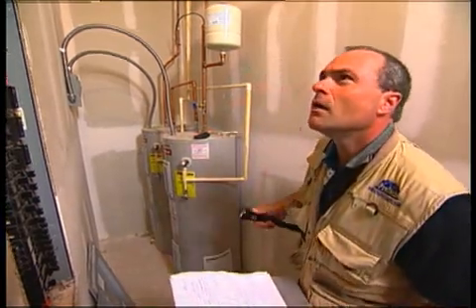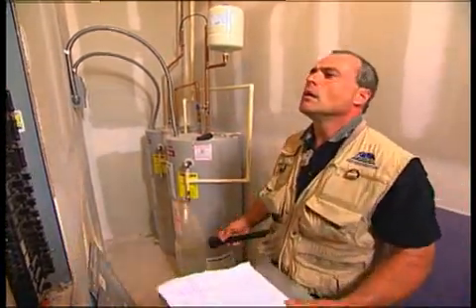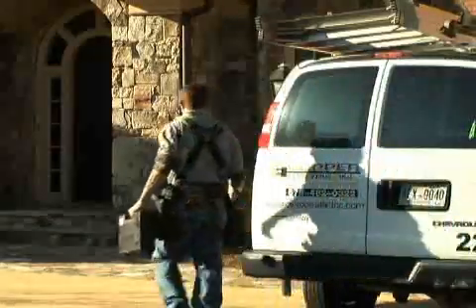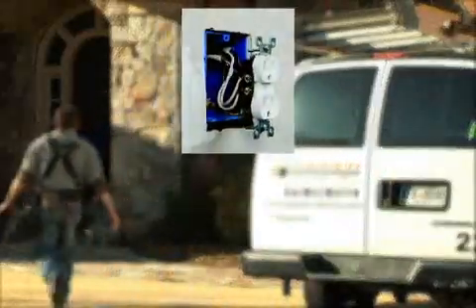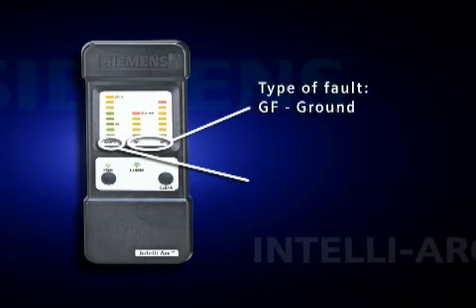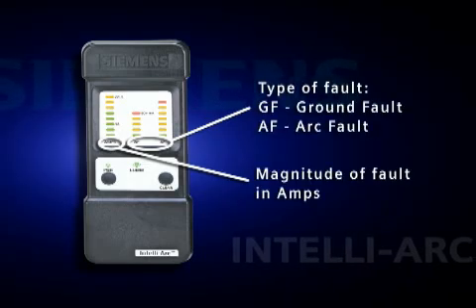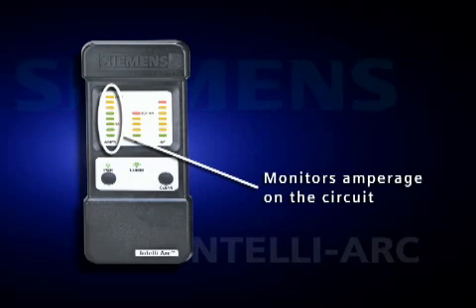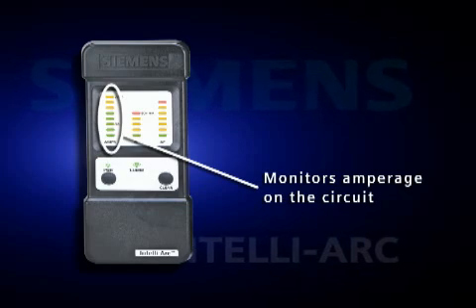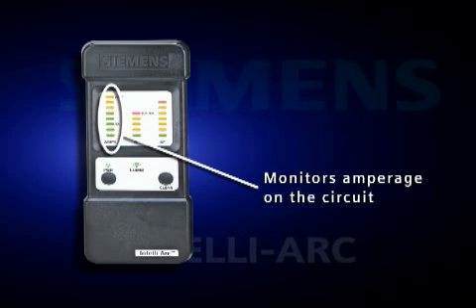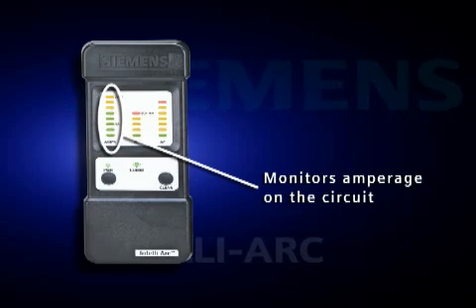Arc faults are often intermittent, which can make troubleshooting a branch circuit very difficult. In these cases, it is important to determine whether the fault condition exists in the permanent wiring, in connected equipment, or in a power cord. The IntelliArc Diagnostic Tool presents information as to the type and magnitude of fault. Since the fault may not cause an AFCI to trip for various reasons — for example, the duration is too short or the current level is too low — the tool provides an indication showing how close an event is to causing an AFCI to trip.